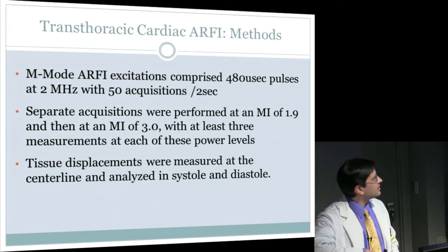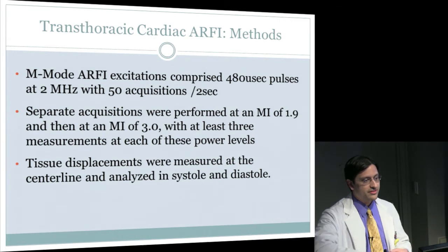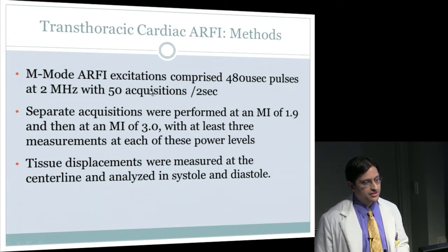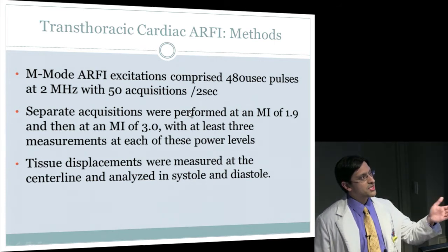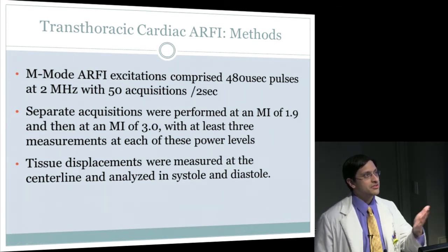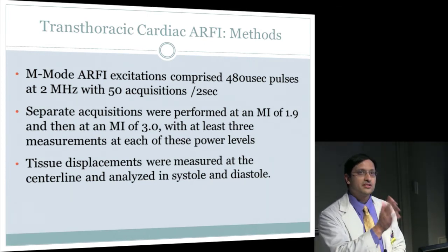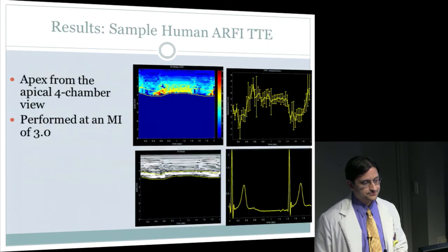The actual RF excitations as well, I won't go into too much detail, but they're less than half a millisecond using a 2 megahertz probe at acquisitions at 25 hertz. And we did several measurements at each of the MI levels in each of the parts of the heart we were interrogating to make sure whether these were reproducible results. And the measurements were measured along the center line of the M mode.